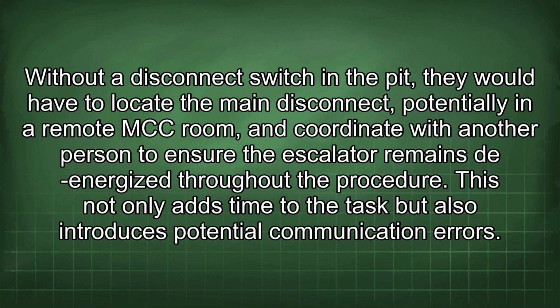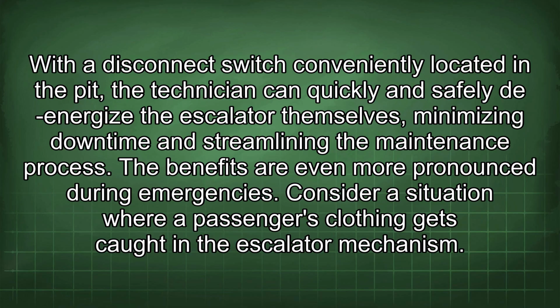Without a disconnect switch in the pit, they would have to locate the main disconnect, potentially in a remote MCC room, and coordinate with another person to ensure the escalator remains de-energized throughout the procedure. This not only adds time to the task but also introduces potential communication errors. With a disconnect switch conveniently located in the pit, the technician can quickly and safely de-energize the escalator themselves, minimizing downtime and streamlining the maintenance process.